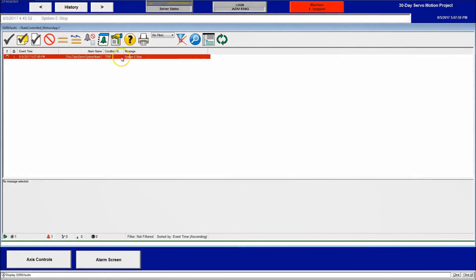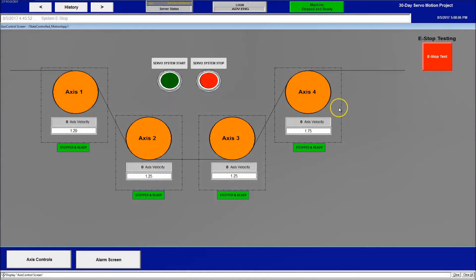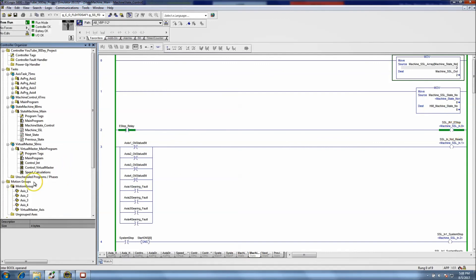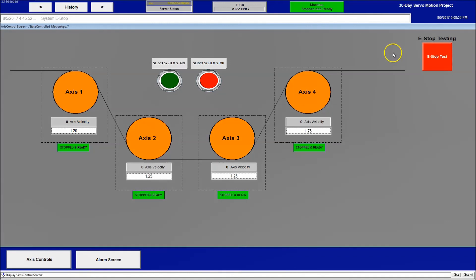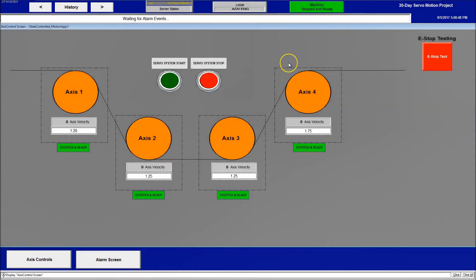If we press stop, the whole system stops based on the state machine. In the fault screen we can see the E-stop is pressed. Once we release it, let's look at what happened in the state machine — the E-stop press took it to state 0. Looking back at the logic, any E-stop at any given time takes the state to 0. It automatically goes back to ready state quickly, from 0 to 1 to 3. It's a really quick transition, so there's no reason to question whether it's working.